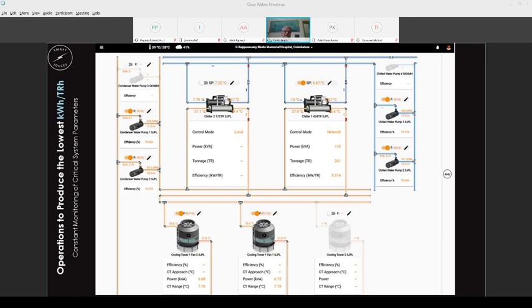So it has its own limit. Like your desert cooler - in a tropical climate like North India, you're able to bring temperatures up to 28, 29 and be comfortable, but not in monsoon. So these cooling towers are able to bring your temperature to a certain limit, which in our industry we call approach temperature. If you're monitoring that approach temperature, monitoring the ambient wet bulb temperature, and monitoring your chiller efficiencies, you can correlate those various data and develop an algorithm with the idea of providing uninterrupted operation of the facility, and at the same time, energy efficiency.